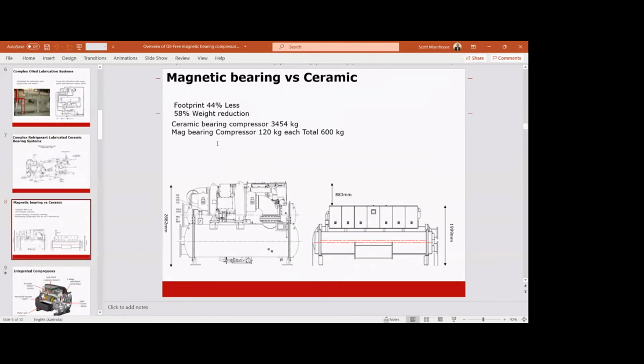So on this slide, if we have a conventional machine, if we have a magnetic bearing versus a ceramic machine, the magnetic machine is 44% less footprint, 58% less weight, and the ceramic bearing compressor weighs 3,500 kilos, where the total compressor of the same capacity on magnetic bearing only weighs 600 kilos. So significant difference when we're using these low pressure machines. So for replacement, these low pressure machines may not fit into the existing plant room. So we have to be very careful of that.